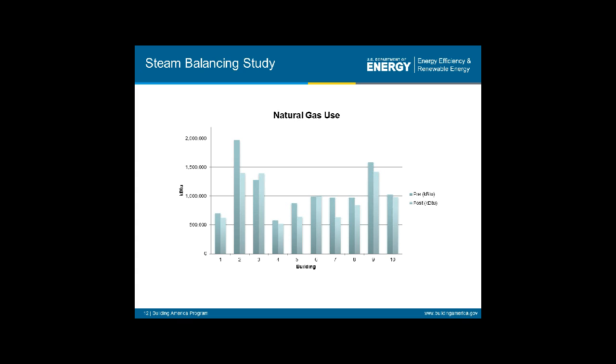And basically, we had 3 big conclusions in general about steam balancing. One, it is an iterative, multi-stage process. You really have to have a conversation with the building manager and tenants, and really take a close look at temperature data before you start swapping out vents or considering resizing risers or header piping. It's really important to consider the building layout, the piping configuration, and the locations of the units which are over- or underheated. And then again, the cooperation of tenants and building managers is really crucial.